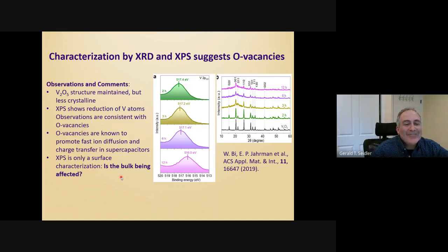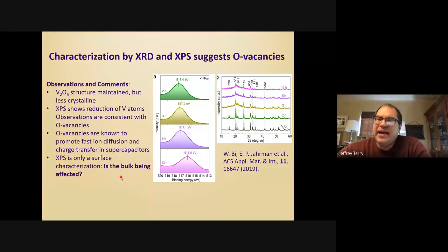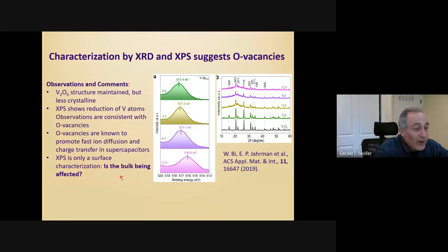That'll go over well. All right. So we have another question. Yes, please. Why is the X-ray power limited to 100 watts? Oh, it's not limited. It's that that particular X-ray tube is limited to 100 watts because we wanted something that was air cooled, so that it would be easy to operate and easy to move, which was needed for some of the early monochromator designs.